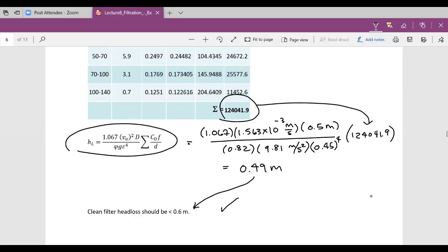Now, if that hadn't been the case, what would we do? Our only real options are to change the approach velocity, change the depth, or pick a different sand to change the porosity. Once we start operating the facility, changing the porosity is not an option. Changing the depth is not an option. The only thing we can change is our approach velocity, but that's dependent on demand.